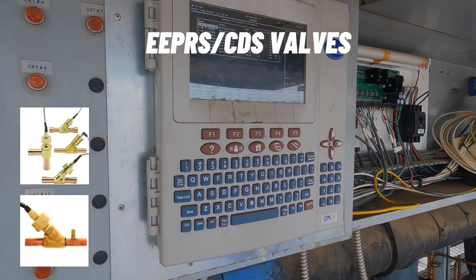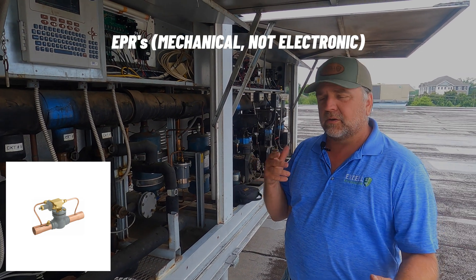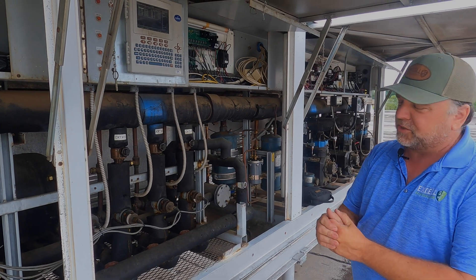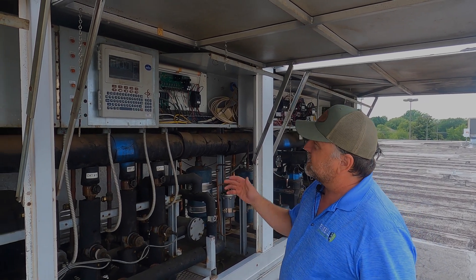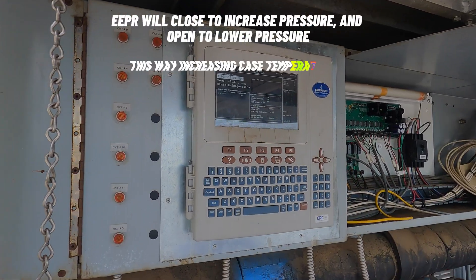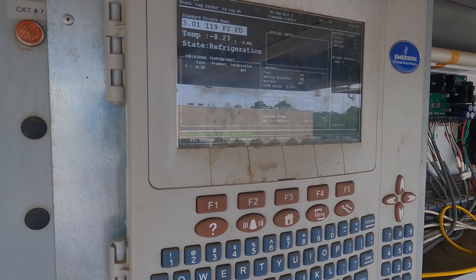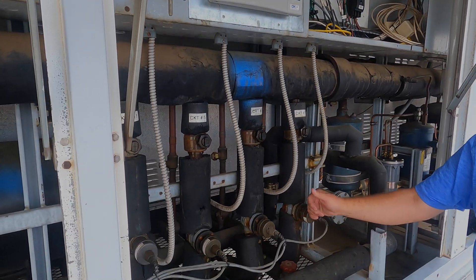We have what we call an electronic evaporator pressure regulator — EPRs are the mechanical version, but these are electric. The computer will drive this valve; in the field we call them CDS valves (made by Sporlan). It's really an EEPR — electronic evaporator pressure regulator. This computer will say the case is running negative eight degrees and I want that EEPR valve open only seven percent. The valve opens and closes as the temperature tries to meet set point. If the case goes into defrost and warms up, the EEPR valve goes to 100% until it reaches set point. That's how the EPR controls temperature.